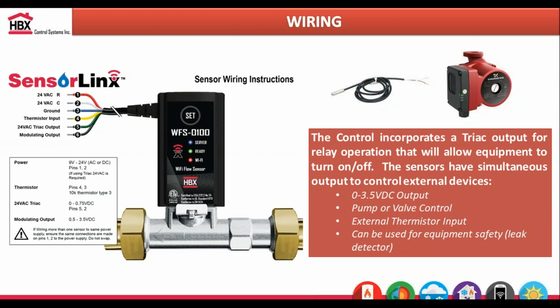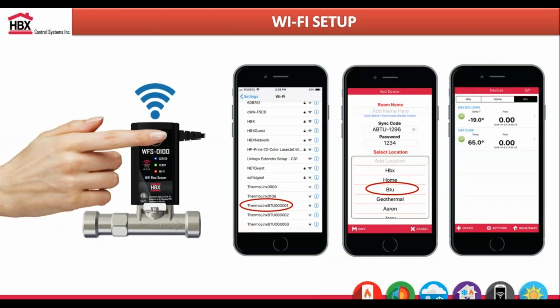There's also a modulating output. If you need us to modulate a pump, at the present time we can do 0 to 3.5 VDC, but later this year we're going to try to get to 0 to 10 in terms of modulating from these sensors. All the communication is built in through Wi-Fi. You just hold a set button on the SensorLinx sensors, connect to whatever Wi-Fi is available, and that's it.